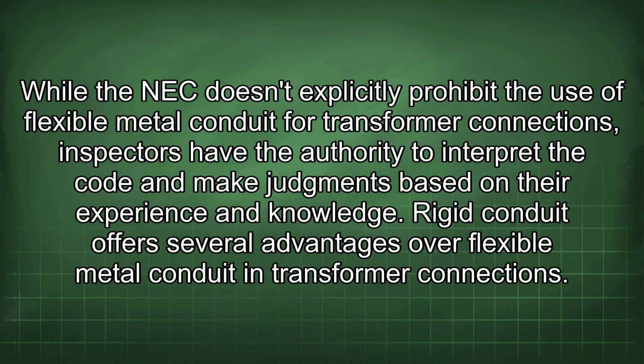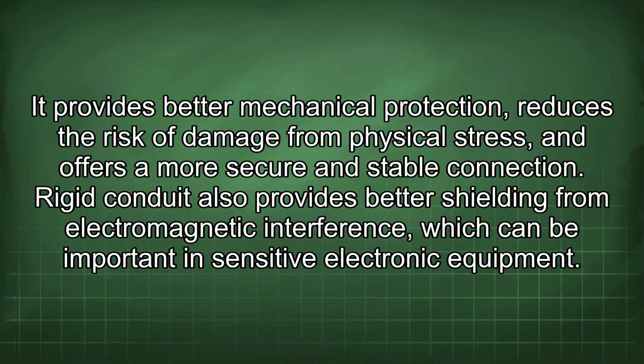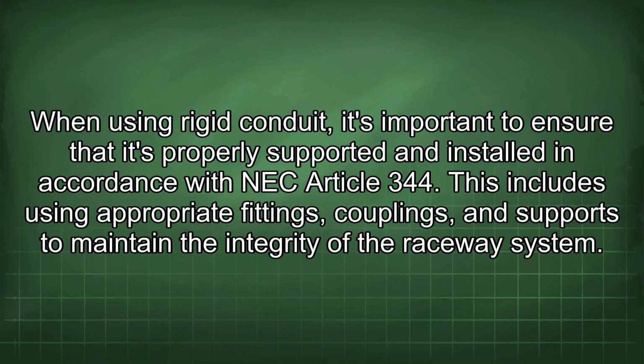Rigid conduit offers several advantages over flexible metal conduit in transformer connections. It provides better mechanical protection, reduces the risk of damage from physical stress, and offers a more secure and stable connection. Rigid conduit also provides better shielding from electromagnetic interference, which can be important in sensitive electronic equipment. When using rigid conduit, it's important to ensure that it's properly supported and installed in accordance with NEC Article 344. This includes using appropriate fittings, couplings, and supports to maintain the integrity of the raceway system.